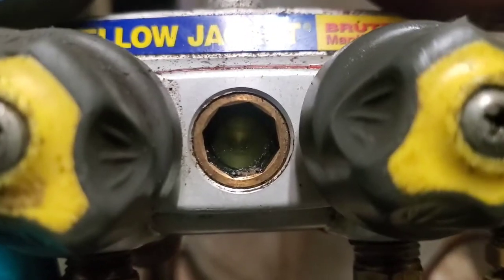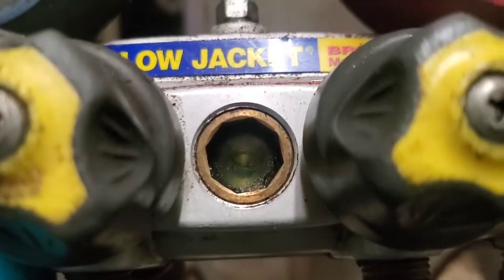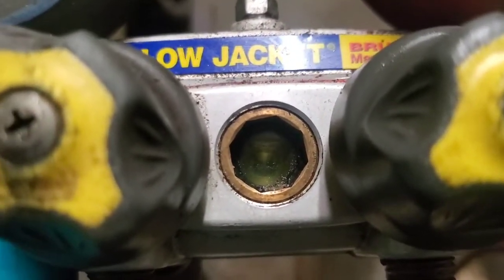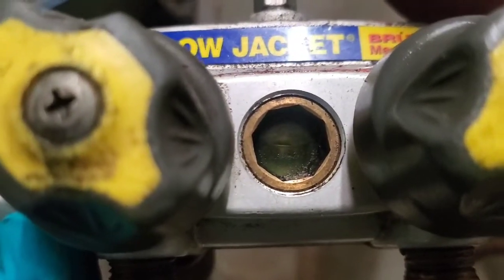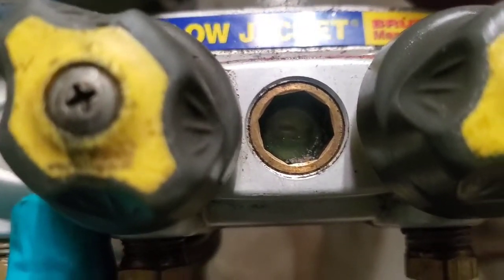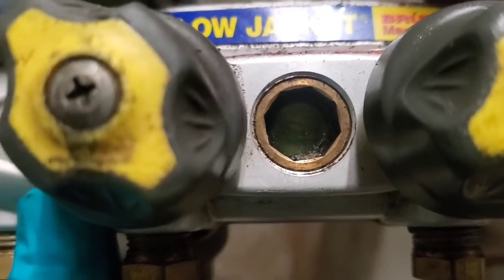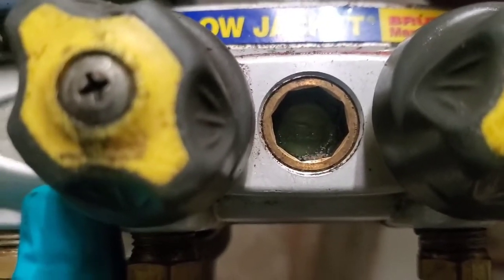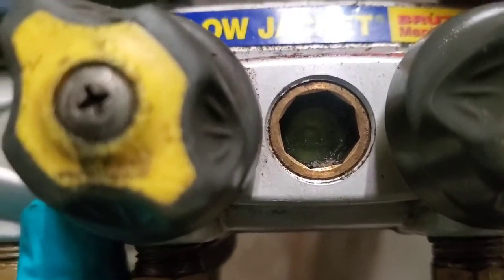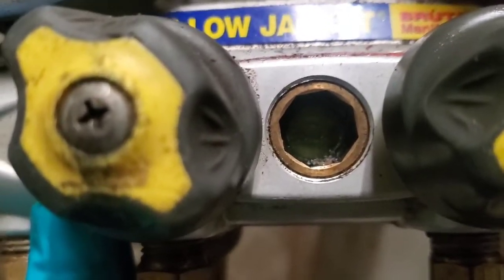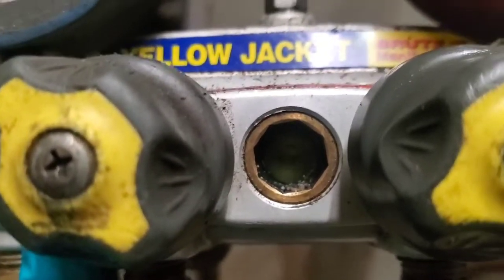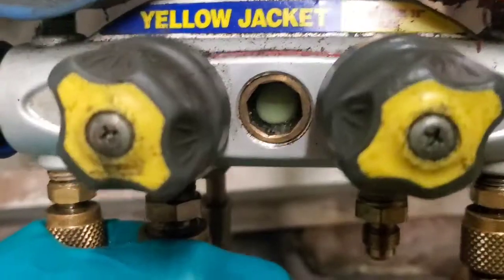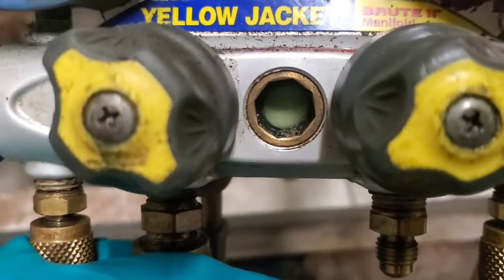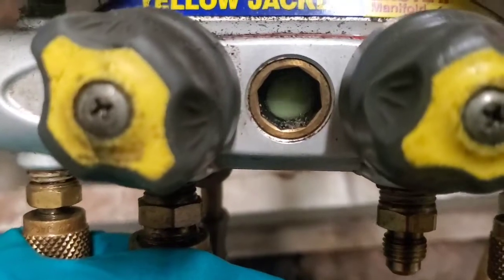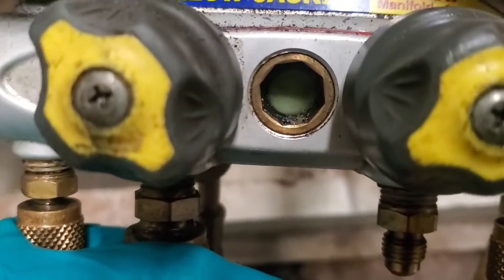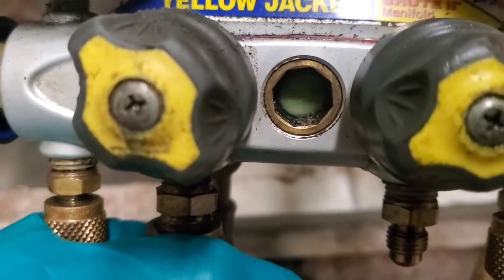So this sight glass is now filled with oil. It's kind of hard to tell, but pretty soon we'll see the oil go away and it get replaced with refrigerant. And actually you're seeing that right now. We're pushing all the oil out of the circuit that we're going to be working on through these gauges and replacing it with clear refrigerant. Once that happens, we'll get the refrigerant out next. And the oil is starting to dissipate. That foam you see is just a remainder of the oil mixed with refrigerant vapor.